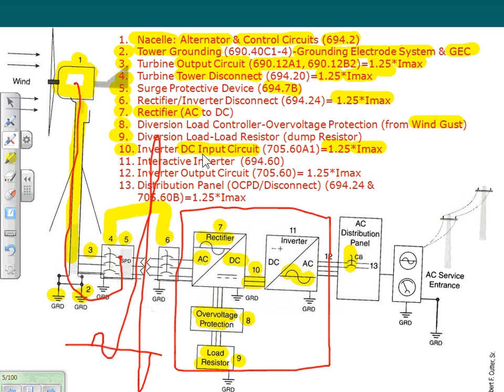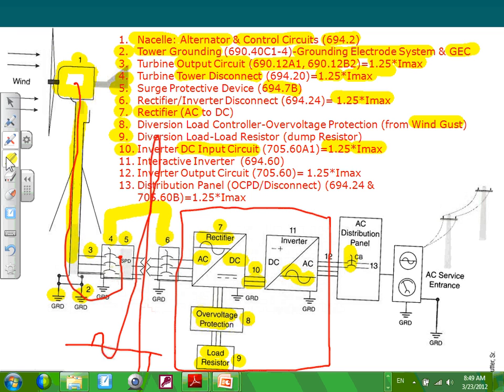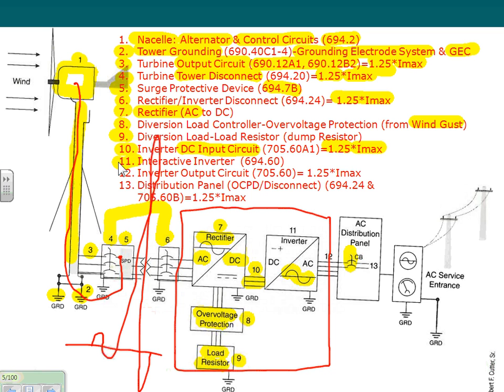Okay, so we got the DC output. If we go back to my inverter, number 11, that's the inverter. The job of the inverter is to have a smooth frequency, a smooth voltage to match the system that you have. 480, 277, 60 hertz, 50 hertz, mostly 60 hertz. So that's the piece of cake. Inverter output circuit, number 12. We captured the right frequency and the right voltage, and we're ready to dump it into the grid, right? So let's say 208, 120 at the right frequency, and now we're tying it to your main distribution panel.